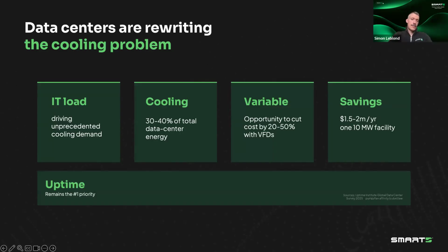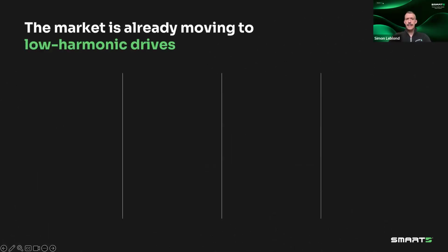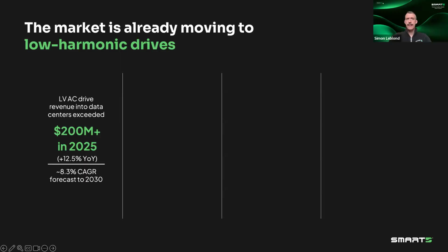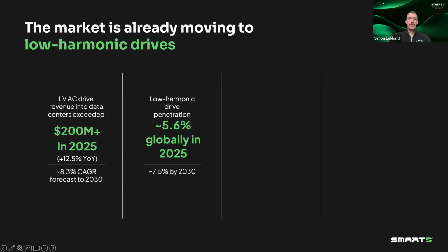That being said, it's not because you're saving money that you want to compromise on uptime. That remains your number one priority, and it's how do you reconcile those two facts together that we're going to be looking at. In terms of landscape, the market for VFDs in data center has been growing. So last year, 2025, over 12% year over year growth. And we are seeing a trend to using low harmonic drives. So, full disclosure, I don't have specific data of low harmonic drive in data center, but we are seeing that market grow with about 11% penetration in North America.